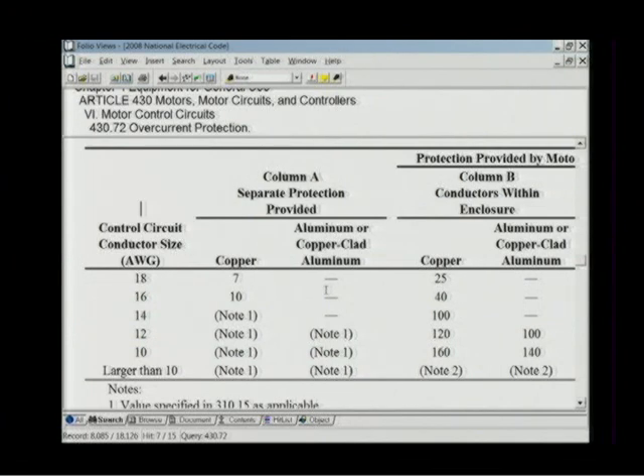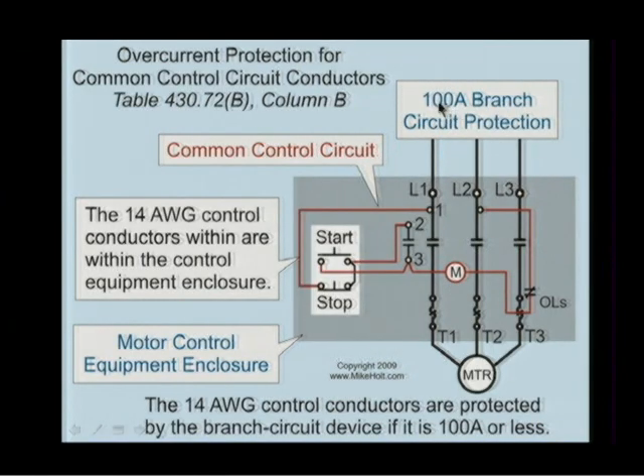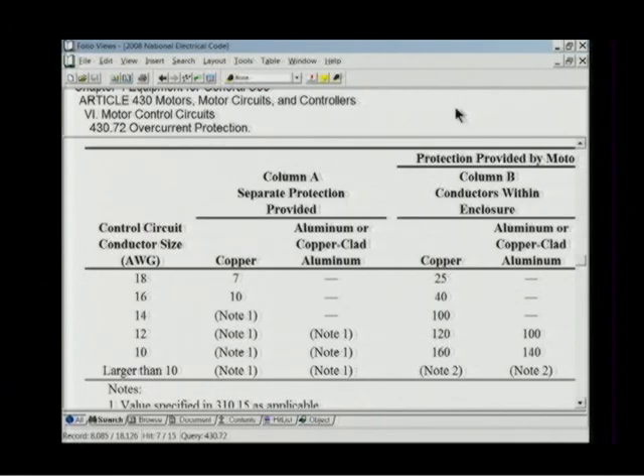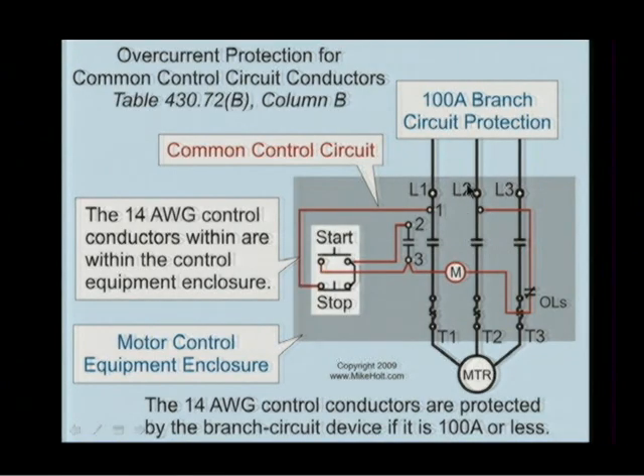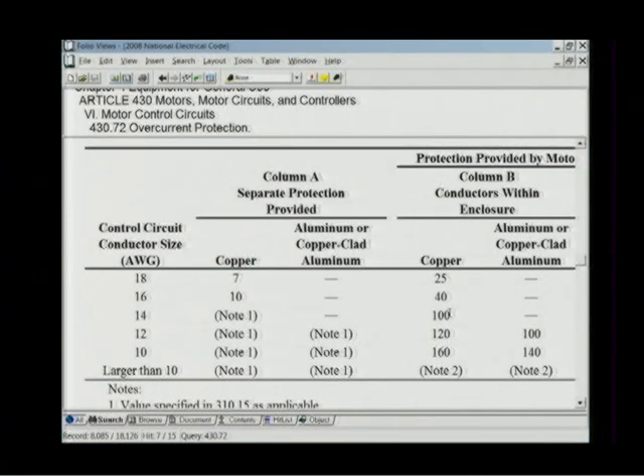If you have 18-gauge wire, then the manufacturer would be able to tap off of a controller circuit as long as this device didn't exceed how many amperes? If it was column B with 18-gauge wire, what would it be? 25 amps, so this would be a maximum of 25. And if they had a starter with 16-gauge wire, then the maximum branch circuit it could be connected to up here would be 40 amp. And 100 amp would be good for 14-gauge wire.